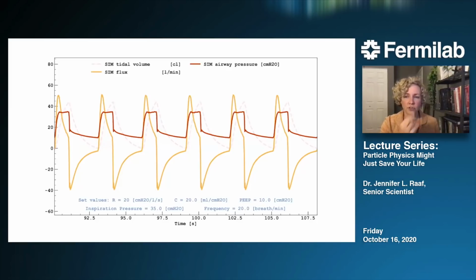The waveforms that you're seeing are what the breathing simulator measures as being provided by the MVM. So those are the airway pressure in dark red, that square wave, the airflow in orange or yellow, and the volume of air in the dashed pink line, which you may not be able to see that well. You can also compare what you see in these waveforms with what some of the set values were, which are the numbers in blue at the bottom.